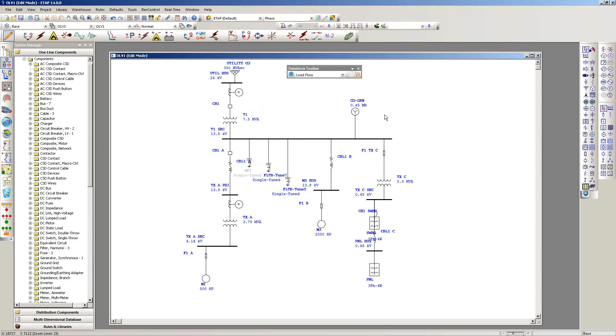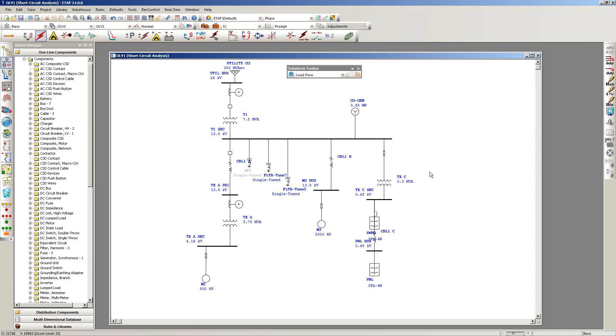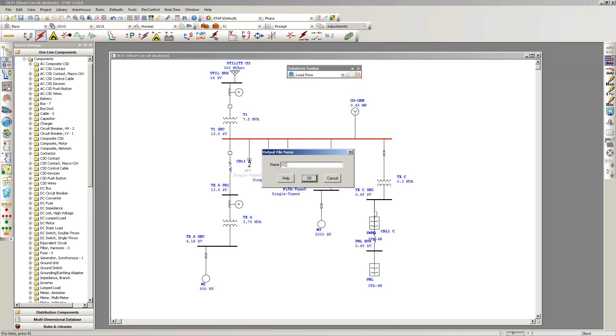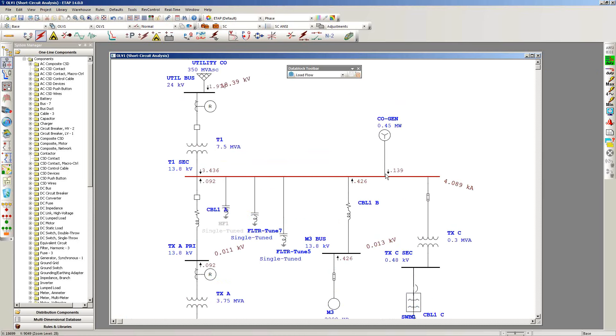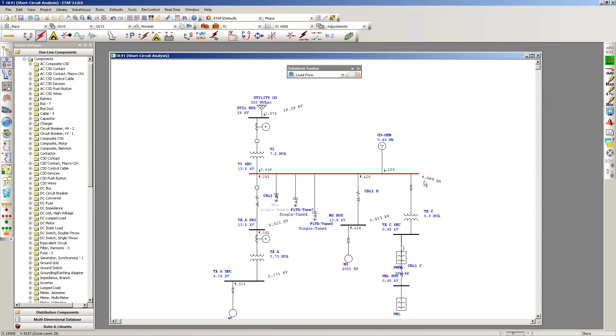Another simulation to perform is a short circuit analysis. I'll switch to short circuit analysis mode to verify that all impedance information from the generator, transformer, and protective device settings including interrupting rating and max kV has been brought over. I'll select a bus location, add a fault, and perform an ANSI three-phase device duty evaluation — calling this 'Short Circuit ANSI Report.' The results show different contributions from the utility and generator, and the total bolted fault at the bus location, confirming all impedance information has been imported successfully.